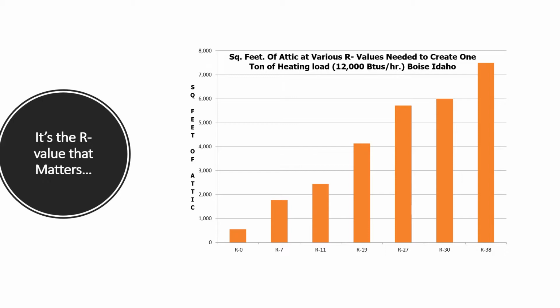So we hear a lot, why can't we just size by square foot? And really, more than square footage, it's the R value that matters. Over here, we can say basically this is the square feet of attic at various R values needed to create 1 ton of heating load, that's 12,000 BTUs per hour, in Boise, Idaho. If you had an R0 attic, it would only take 500 square feet to create that 12,000 BTUs, or 1 ton of load. By the time you get to R19, a big difference, you'd need 4,000. But with today's homes, a lot of them having R38 or higher, it takes 7,500 square feet.